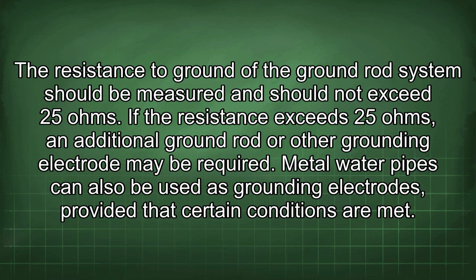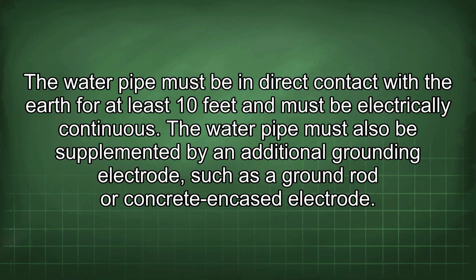Metal water pipes can also be used as grounding electrodes, provided that certain conditions are met. The water pipe must be in direct contact with the earth for at least 10 feet and must be electrically continuous. The water pipe must also be supplemented by an additional grounding electrode, such as a ground rod or concrete encased electrode.